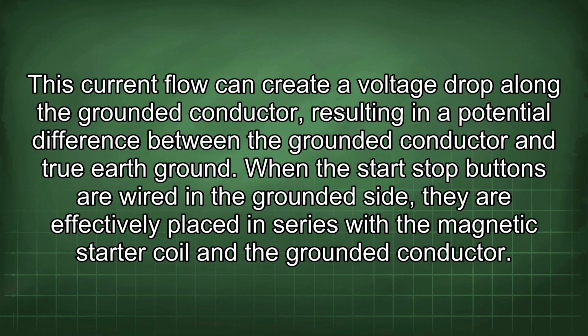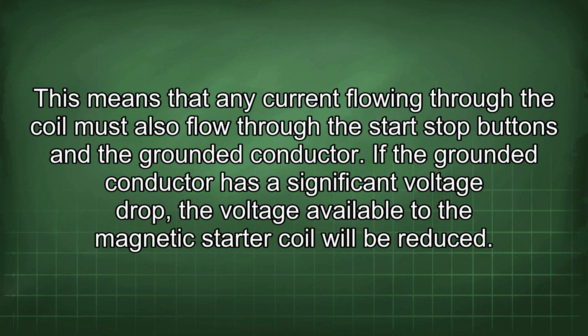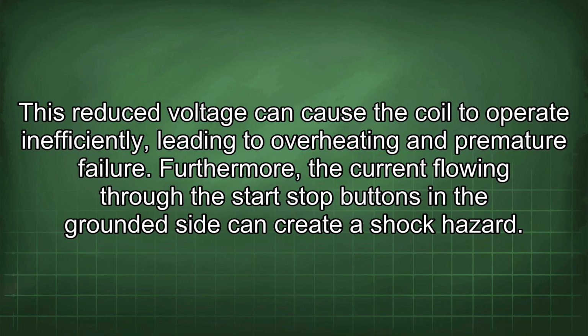When the start-stop buttons are wired in the grounded side, they are effectively placed in series with the magnetic starter coil and the grounded conductor. This means that any current flowing through the coil must also flow through the start-stop buttons and the grounded conductor. If the grounded conductor has a significant voltage drop, the voltage available to the magnetic starter coil will be reduced. This reduced voltage can cause the coil to operate inefficiently, leading to overheating and premature failure.